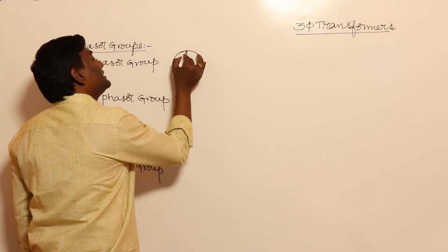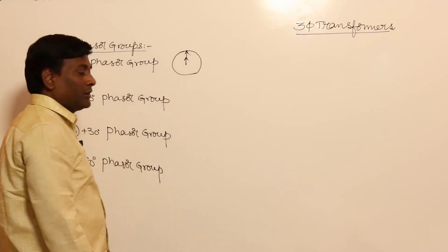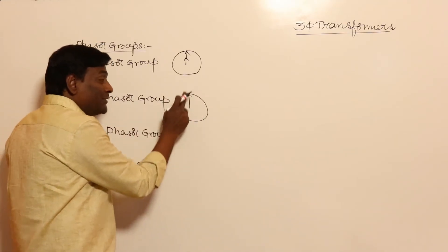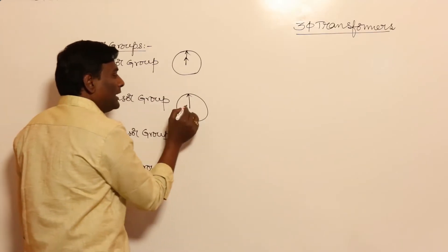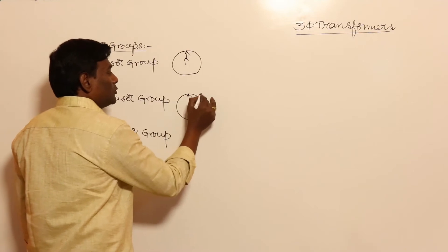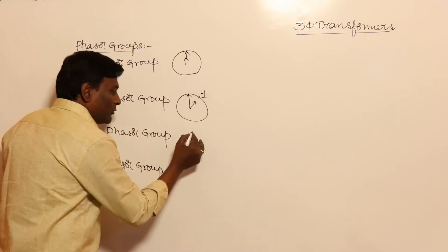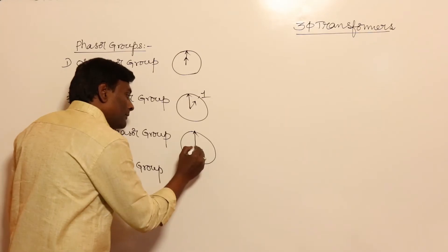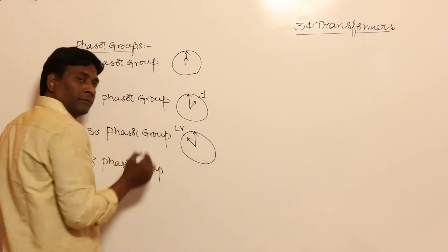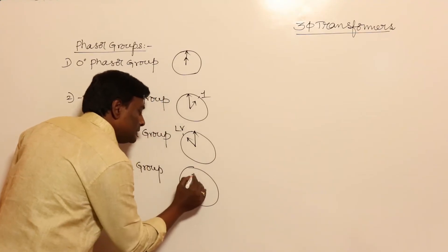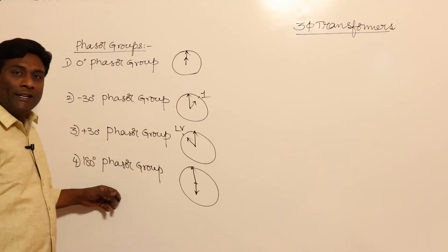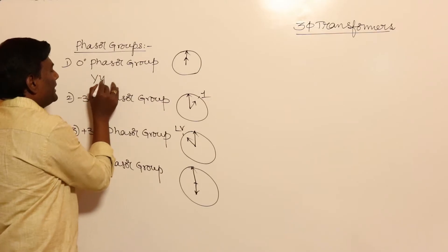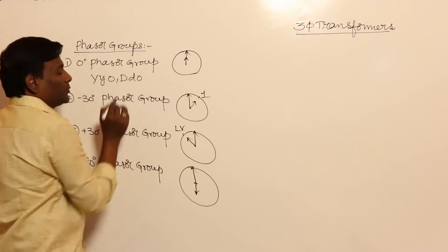If I draw the clock diagram: for 0 degrees, HV is here and LV is also here. For minus 30 degrees, HV is here and LV lags, so LV is at position 1 on the clock. For plus 30 degrees, LV leads HV. For 180 degrees, LV is on the opposite side from HV.